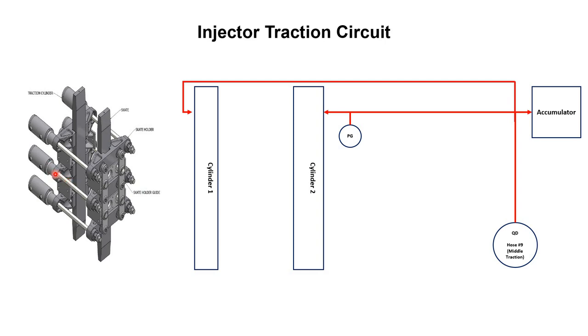For the middle pair of cylinders, the circuit starts from hose number 9, which is the quick disconnect. From this hose connection, pressure will go to the accumulator. From the accumulator, we have a T-connection where the flow will be divided into two parts. One hose from the accumulator will go to one cylinder and the other hose will go to the other cylinder. At the cylinder, we have a pressure gauge which will show the pressure of this circuit.